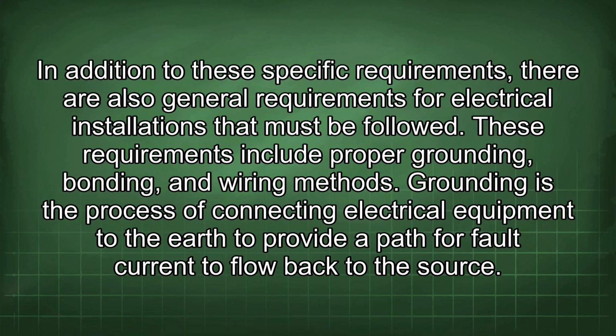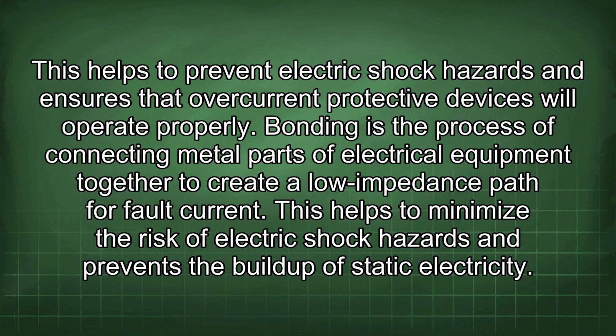In addition to these specific requirements, there are also general requirements for electrical installations that must be followed. These requirements include proper grounding, bonding, and wiring methods. Grounding is the process of connecting electrical equipment to the earth to provide a path for fault current to flow back to the source. This helps to prevent electric shock hazards and ensures that overcurrent protective devices will operate properly. Bonding is the process of connecting metal parts of electrical equipment together to create a low impedance path for fault current. This helps to minimize the risk of electric shock hazards and prevents the buildup of static electricity.